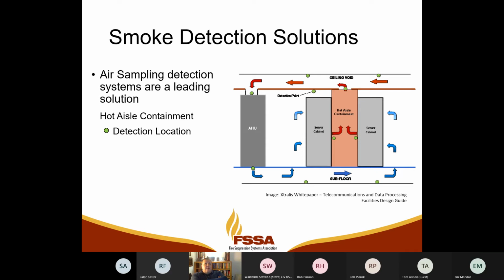That was really in those code discussions, the telco guys, their experience came out very strong, that they have used as a practice putting air sampling at return grills in their facilities for years, and they catch smoke events that way, and they catch them early, and they get to address them. And it's not their spot smoke detectors that help them catch fires in their building, it's their air sampling. And as far as sensitivity of the holes, NFPA 76 has that guidance on how to set up for sensitivity, and I think that's now in NFPA 75 too also.